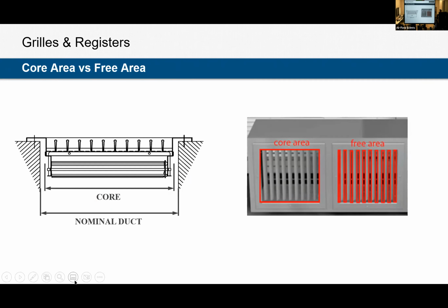Now we're looking at actual size of grills. The size that you would be selecting or scheduling, usually you're looking at a nominal size. I need to cover this opening. This is the size grill I need. The actual air outlet is always going to be a smaller dimension than the opening that we're covering. That's your core. The core is what our air is actually coming out of. And then within that core, you're probably going to have some reduction of free area. So even though our core is X size, there could be blades or dampers or something in that airstream that is actually reducing the air outlet to a much smaller free area. So we start with a grill as big as the nominal size, and we're actually down to this small amount of free area that air can actually pass through.